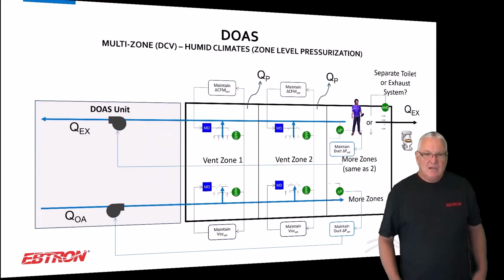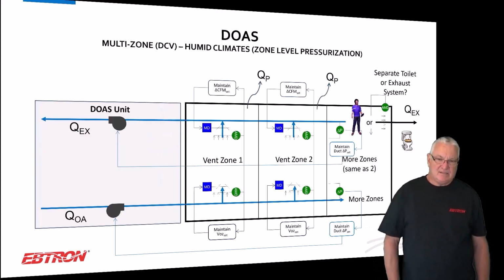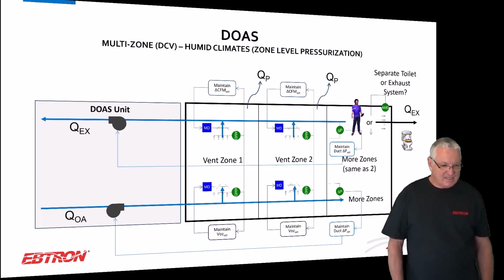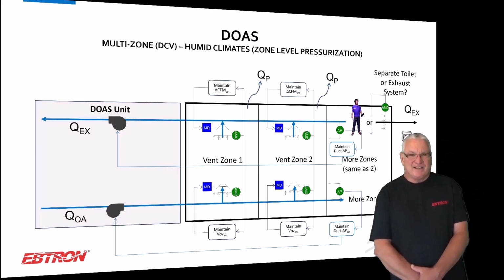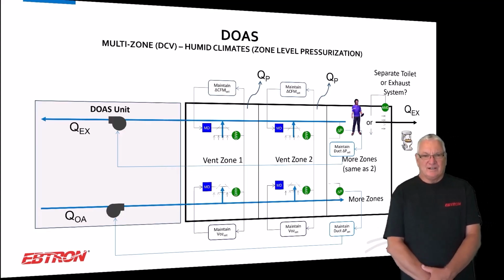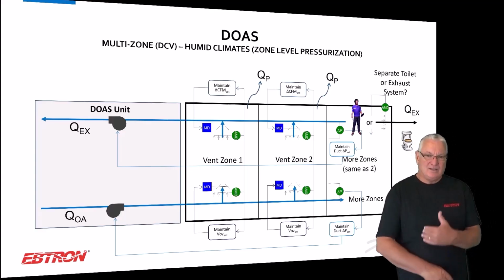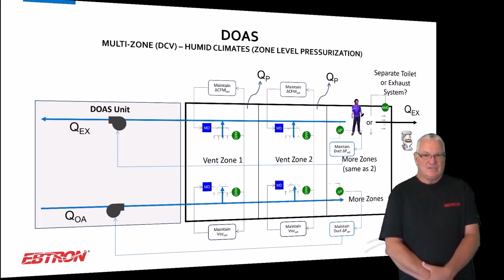Okay, same deal. When we get into really humid climates, and it's a lot of them. I say really humid climates. It's really anywhere east of the Rockies, but getting people to buy into this has been relatively difficult. You really should treat ventilation zones on a DOAS system not much different than you even think about how you're doing your operating rooms and stuff, meaning that you want to control the ins and the outs because you don't want those individual ventilation zones to go negative in a humid climate. It's a problem. So this is what I'd like to see people do, but they don't do enough of it. Okay.